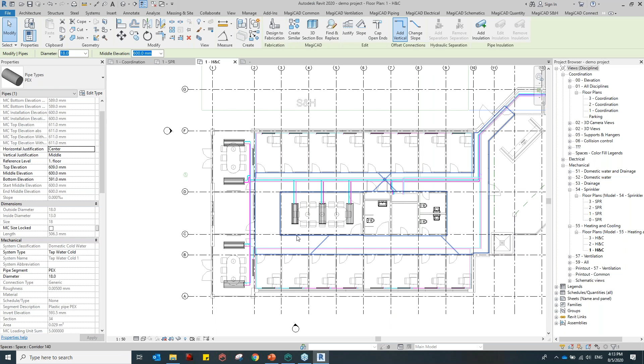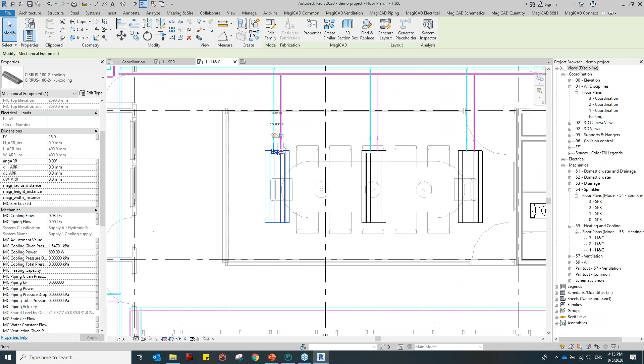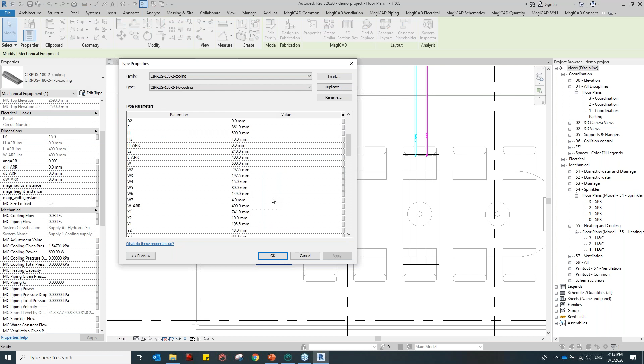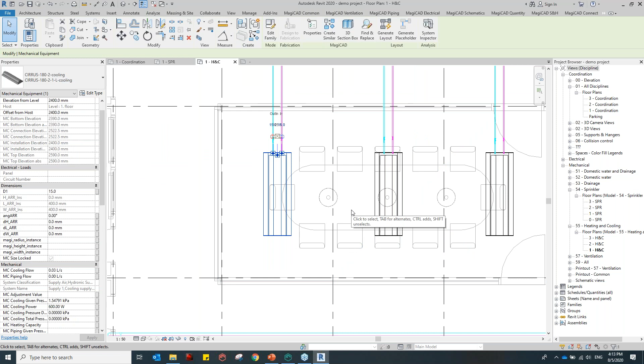The same goes with heating and cooling. Whenever you have a device connected, you need to specify the flow rate for the supply pipe and the flow rate for the return. You can specify that in this model. Once you specify that, you no need to worry about anything, it will automatically follow. MagiCAD will automatically do the sizing and pressure calculation for you.